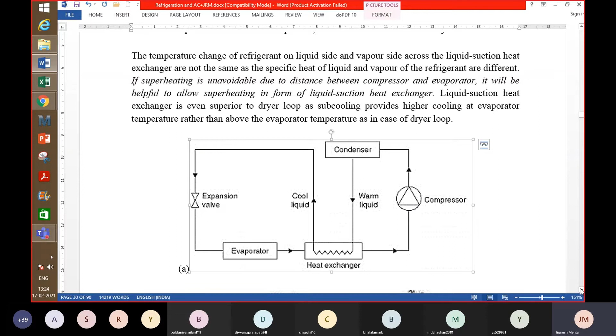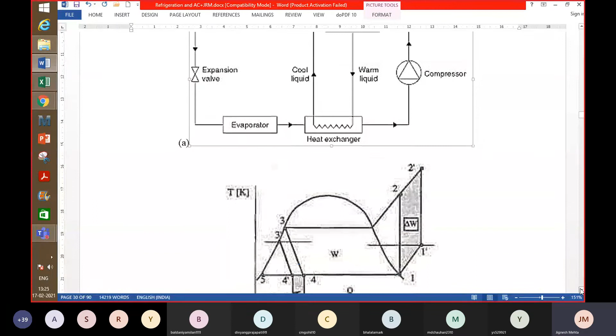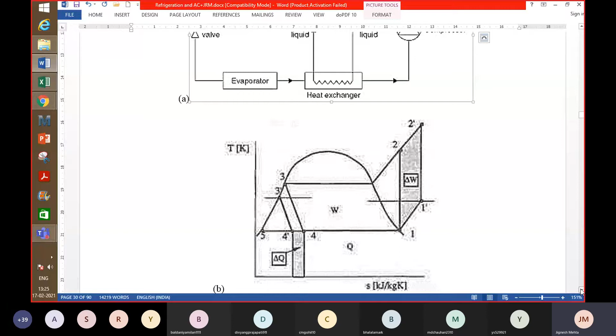So when it comes out of the expansion valve, the dryness fraction would be lower, and that will be beneficial for the cycle as well as for the functioning of the expansion valve. Now, whether you will be able to increase COP this way or not, to understand that, you have to plot it on the required chart. So this has been plotted on the TS diagram, as you can see. Without a liquid suction heat exchanger, it would come out at 1, and then 2, and then 3, and then 4, and 1.